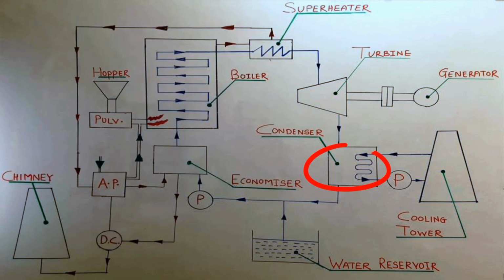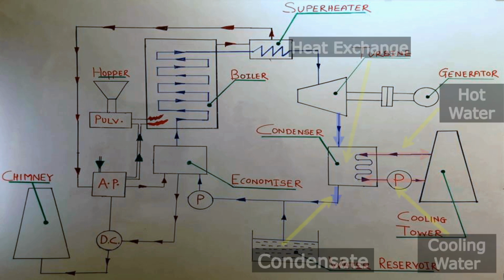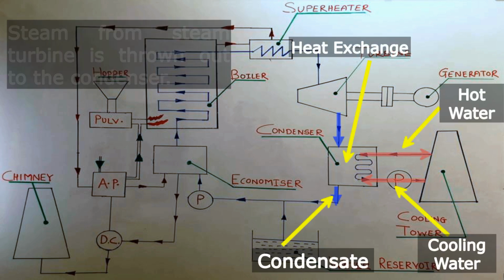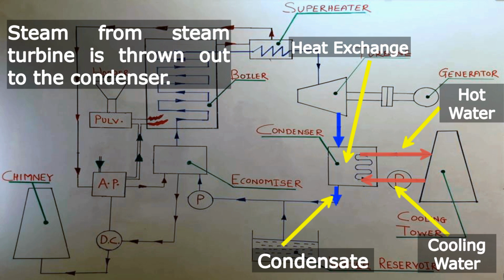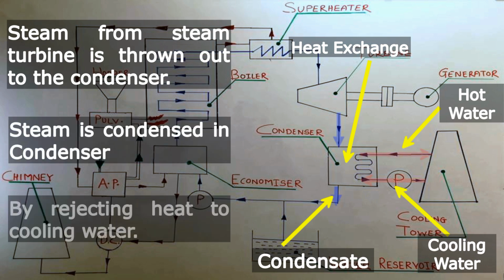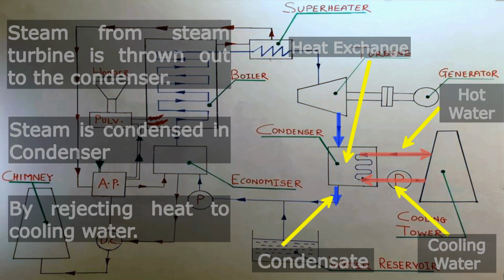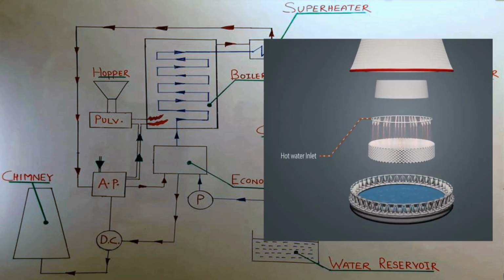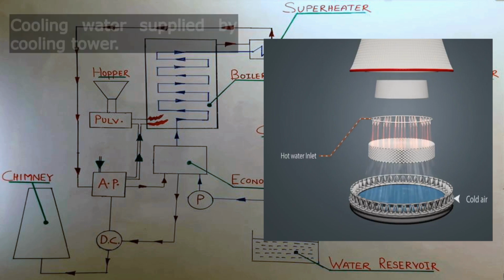Now the next element is a condenser. The steam from the steam turbine is thrown out to the condenser, where the steam is condensed by rejecting heat to circulated cooling water. From the animation, you can see here the cooling water from cooling tower is supplied to the condenser and absorbs heat from the exhaust steam of the steam turbine.